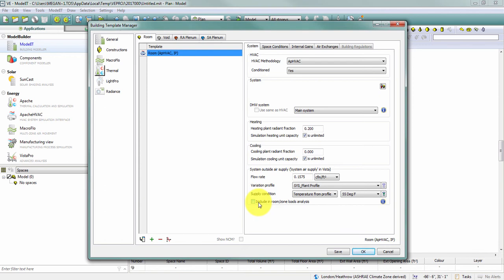So if you leave this box unchecked, that will continue to be the case. And when you evaluate room loads, you'll be looking only at the load in the room. So that's the gains and losses associated with the room, things like solar gain, infiltration, conduction, internal gains from light, people, plug load, etc.